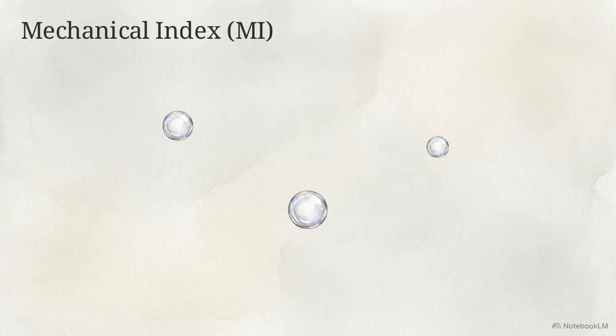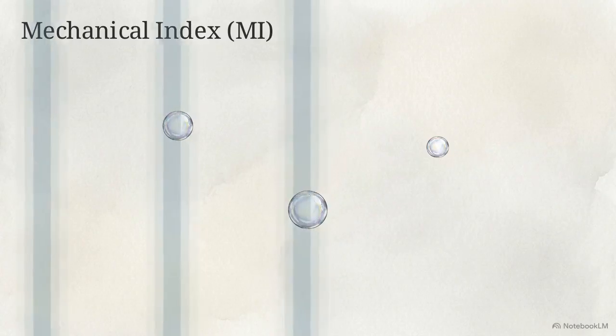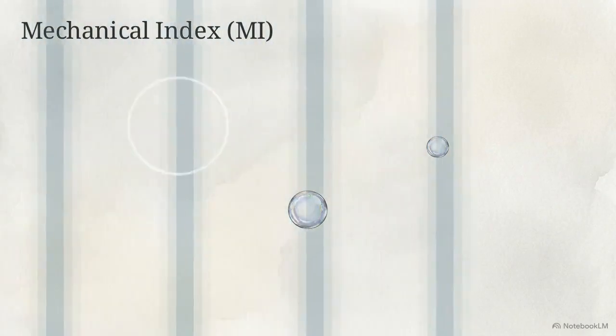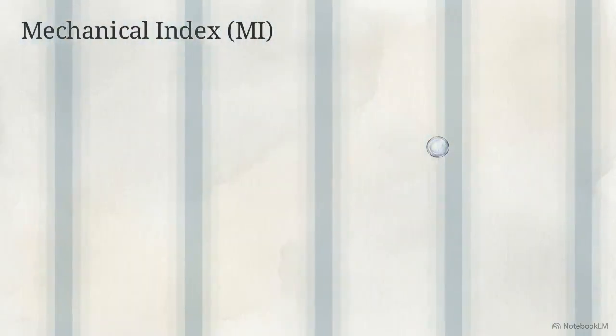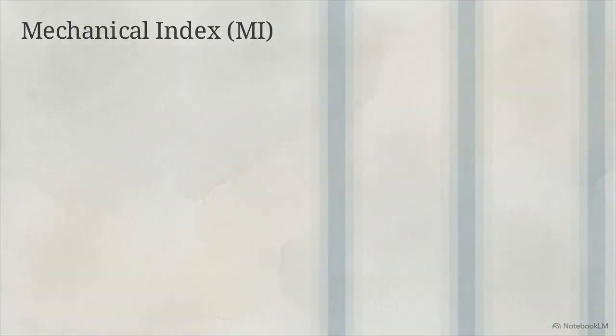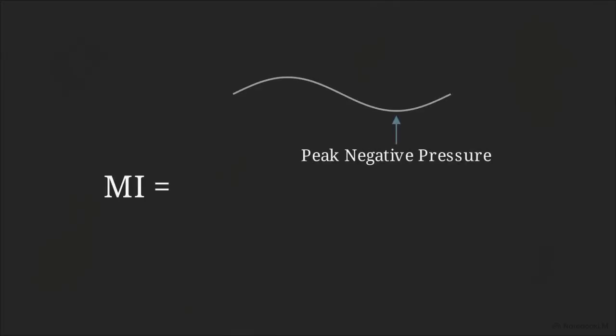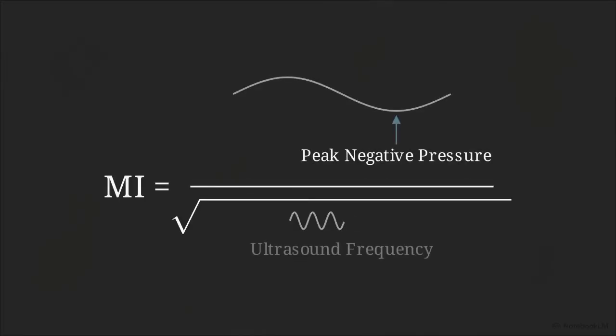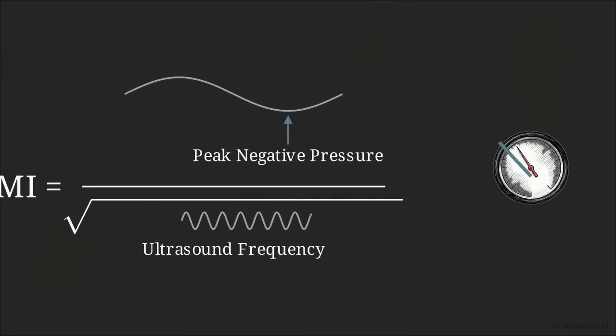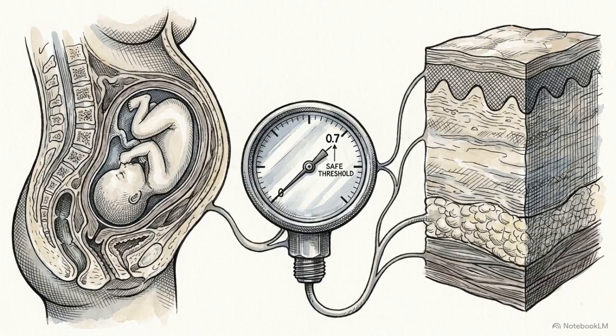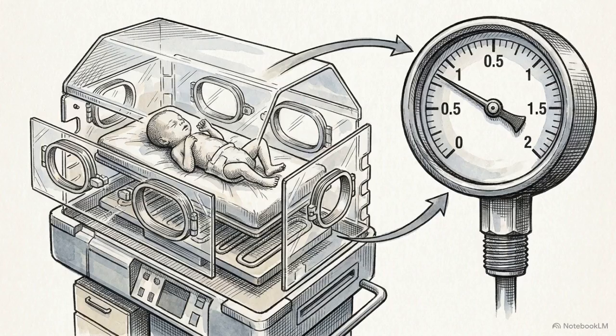This tracks the maximum amplitude of the pressure pulse, which dictates the risk of cavitation. Cavitation occurs when rapid pressure changes from the ultrasound beam force microscopic gas bubbles in biological liquid to expand and violently collapse. The mechanical index calculates this risk by dividing the peak negative pressure of the wave by the square root of the ultrasound frequency. The British Medical Ultrasound Society mandates that the MI must remain below 0.7 for general diagnostic and obstetric imaging and strictly below 0.5 for neonatal scans.